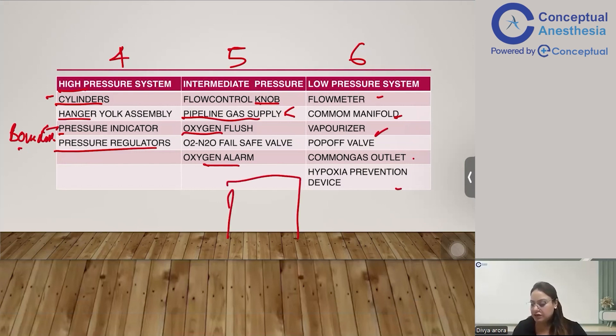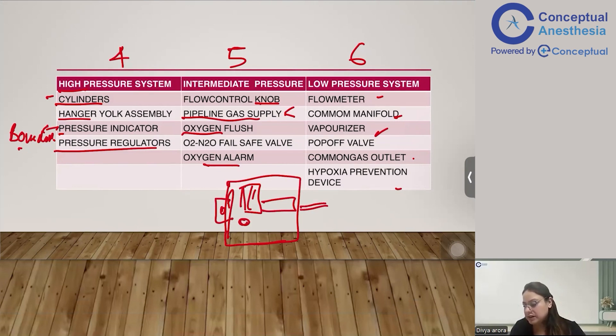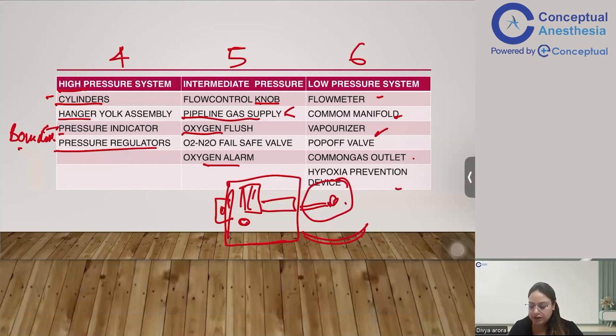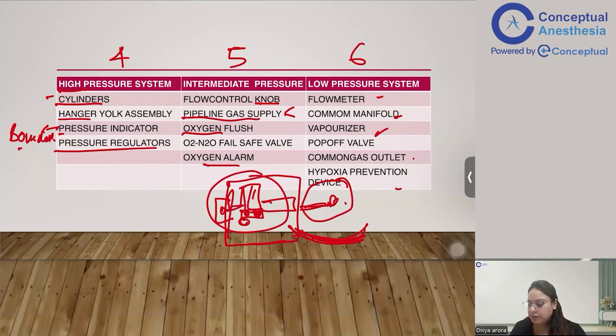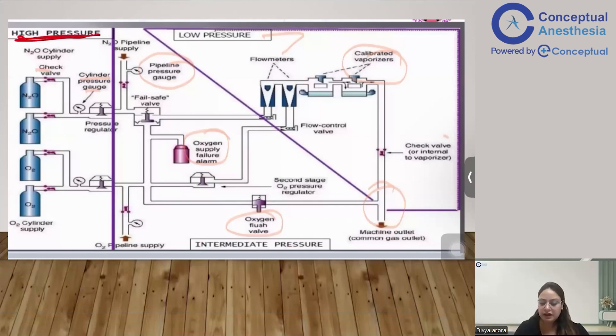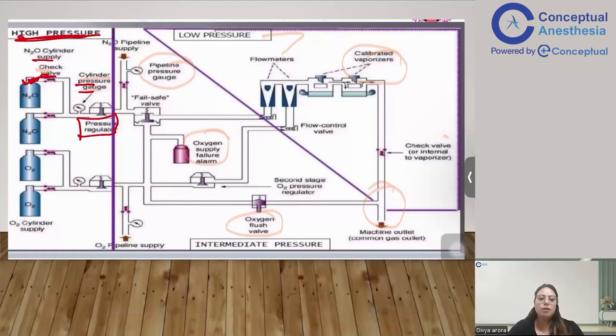To remember this diagrammatically: on the anesthesia machine you have flow meters, vaporizer, oxygen flush, and auxiliary oxygen at the front, and the cylinder at the back with the pipeline connection on the side. Starting from the back — cylinder, hanger yoke assembly, pressure indicator — that is the high pressure system. Everything at the front such as the flow meters, vaporizer, and common gas outlet are the low pressure system.